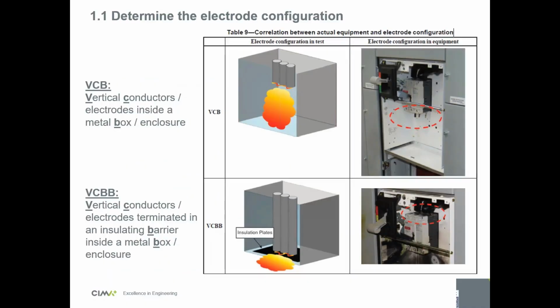So the first step is to determine the electrode configuration. So what is that? Remember that the electrodes are the live conductors. There are the bus bars, and the cable extremities that are unskinned and show live conductors. For example, if you have a short circuit below a breaker here in this cell in the top right, the arc flash will go down in the box. So it won't go perpendicularly towards the worker. It will go down. This is what we call VCB, vertical conductors inside a box. It represents an arc flash going down inside a cell.